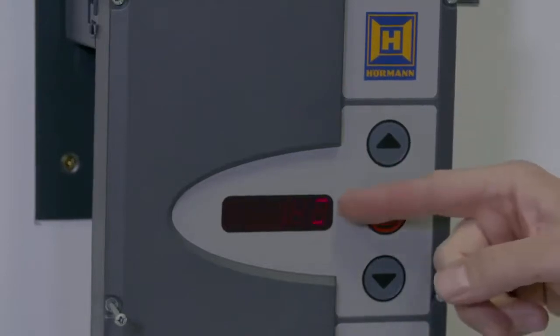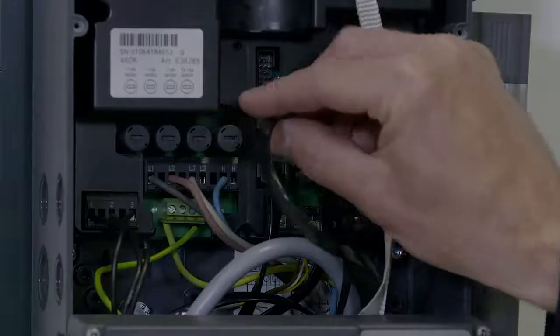If a double line is showing, there's a connection issue with the six core comms cable between socket x40 and the motor.